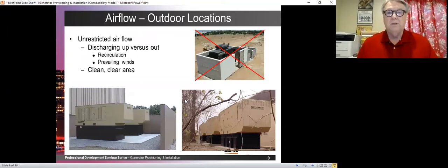Now, airflow is pretty important here. You can see up there in the upper right-hand side, we're going to have a problem there because this is a generator that exhausts horizontally. The air comes out at quite high velocity, goes through that radiator, and when it goes through the radiator, it's going to hit a wall. And that is going to do 2 things. Number 1, it is going to create a high pressure zone in there, which is going to cut down on airflow, which is likely going to cause the generator to overheat. Number 2, it's going to allow that exhaust to circulate around and come back into the generator. So now the incoming air to the generator is hot.